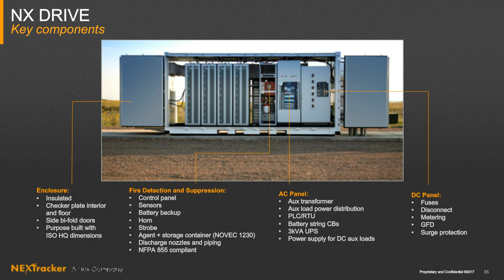So everything's included in here. You've got all your regulatory compliances like NFPA 855, UL 9540. You've got fire detection, suppression, and strobes, and of course the clean agents, all that fire suppression stuff. You've got AC panels, DC panels, all the surge protection, ground fault that comes along with that. And you could get it with or without an inverter, with or without the EMS - we've made it very flexible and scalable so you could plug it into any system, or get it completely wrapped with flex behind it.